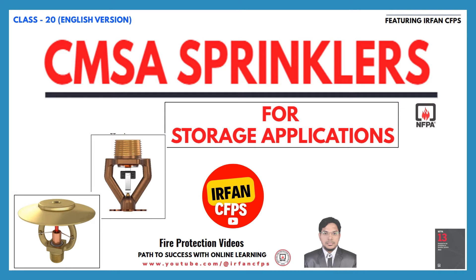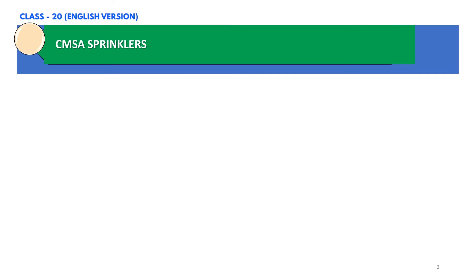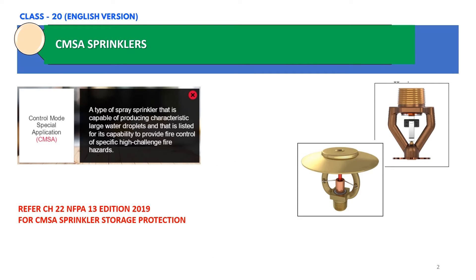Hello everyone, welcome back to my YouTube channel Irfan CFPS. We are continuing our class of NFPA 13 series. In today's session, we are going to understand the selection of sprinkler for storage application based on the CMSA approach. CMSA sprinklers refer to a specific type of sprinkler listed for storage application with increased severity fires. You can refer to NFPA 13 chapter 22, edition 2019, for CMSA sprinkler storage protection. In our next slide, we are going to take one example and try to select the CMSA sprinkler based on that particular scenario.